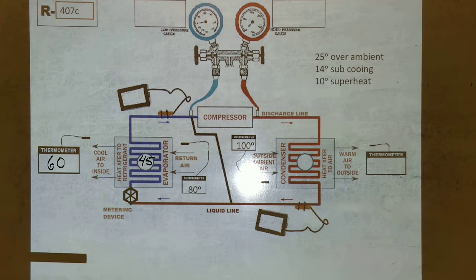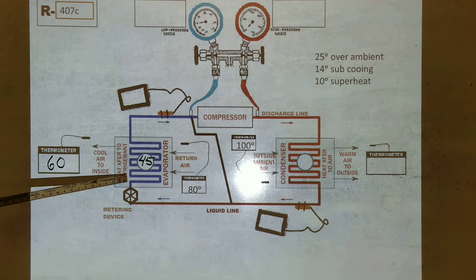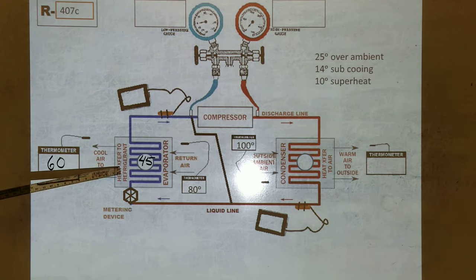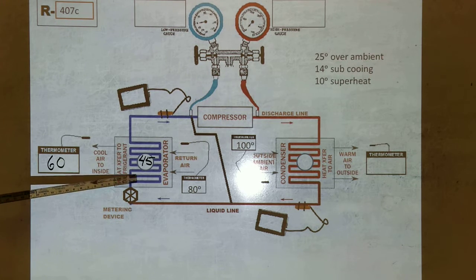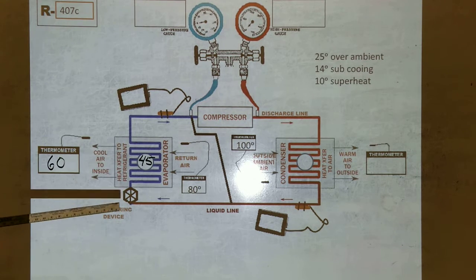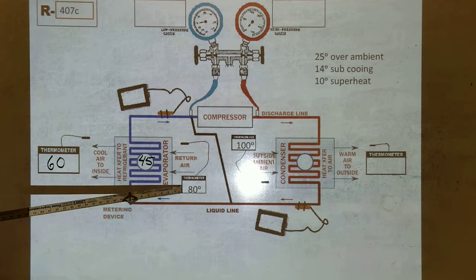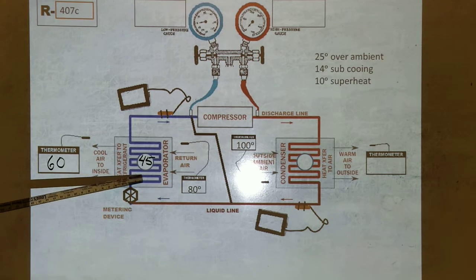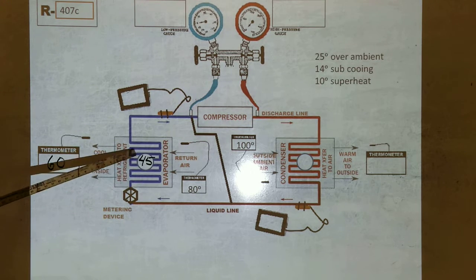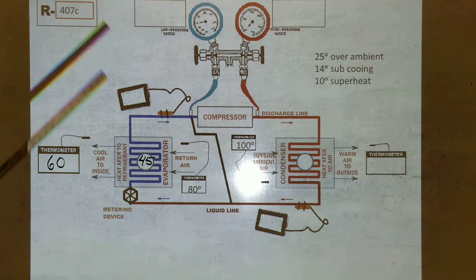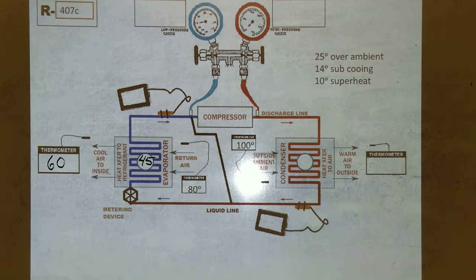Wait, how'd you get it? We put the pressure. How'd you get it? It's a 35 degree difference from saturation. The difference between the return air and the surface temperature of the evaporator. The surface temperature of that evaporator is pretty much the same as the pressure, because that's when the refrigerant is changing states, right?